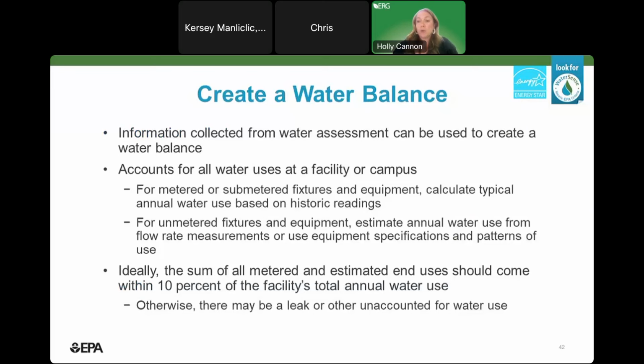Once you're able to conduct the on-site assessment and figure out where water is being used, you're going to create your facility water balance to see if there are any unidentified sources or water losses. The goal is to account for all water use at the facility. This can be done using metered or sub-meter data, engineering estimates, or other calculations based on flow rates, flush volumes, and other equipment specs you collected on site.